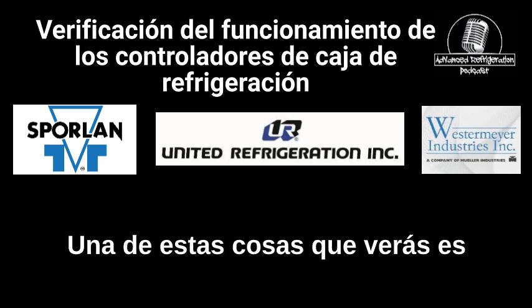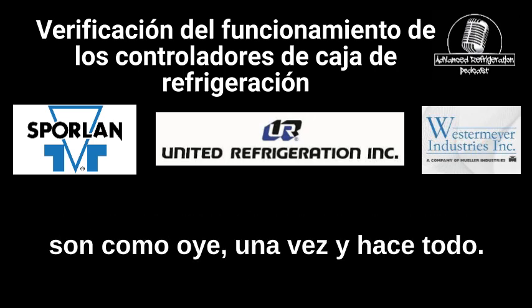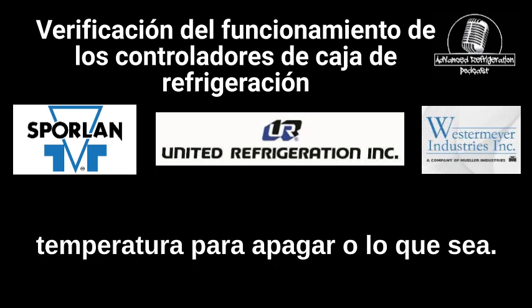One of these things that you'll see is you have the Dixell controllers that basically come from United, that come in a package that does everything. I had one of those have a sensor go bad. It just opened up and caused the case temperature to shut down or whatever.